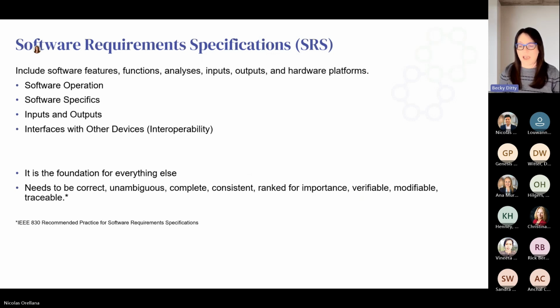Your tests are according to your requirements, so your requirements need to be specific. If you're a device that's taking a recording from a patient, it's not just that the system shall require a recording to be taken, but how long does that recording need to be? Is it 30 seconds? Is it 45? Is it 50? And then you may have a requirement about what's required if it's not 30 seconds or if it's longer. The user needs to take a new recording.